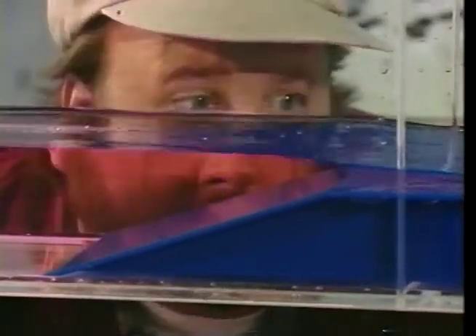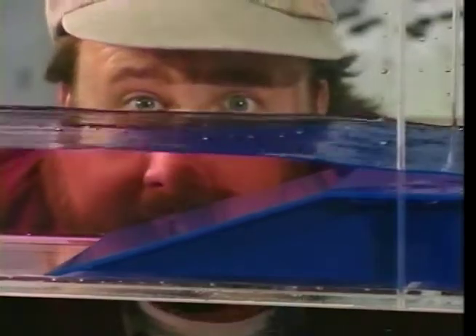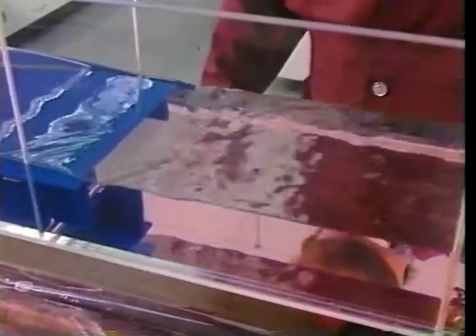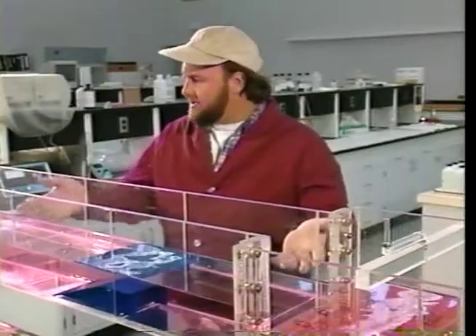In the lab with a scale model of a broad-crested weir, there's no stilling pool because the approach velocity is not as critical as with other devices. When water flows over the ramp, it accelerates and contracts; then below the weir, the water slows and expands. Look for this contraction in the water surface to indicate the broad-crested weir is measuring accurately. However, if the downstream water level is tweaked to flood out the weir, the contraction and expansion pattern disappears — and your measurements are basically a wash.